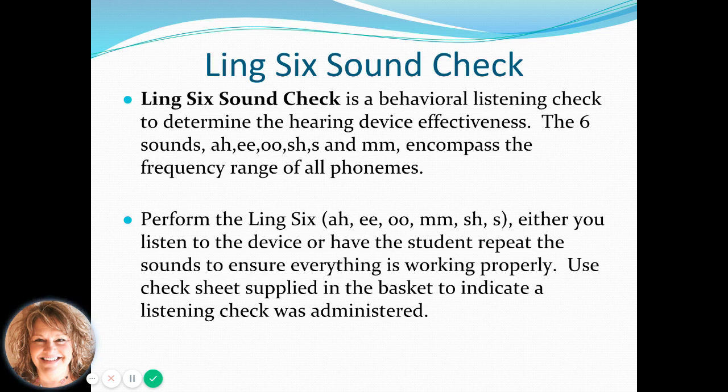You want to perform that either by listening to the device yourself and hearing those sounds, or having your student wear the hearing aid while you talk into the microphone at a distance and have them repeat those sounds. The main thing is to change up the sounds in different order. Don't always do the same thing, or you'll find that the student is just repeating what you say over and over. Even if it's a quick, hey, what'd you have for breakfast? Or depending on their age, you could say, touch your nose as you're walking away. Something where you know that the microphone is working and your voice is being sent to their hearing device, you know by how they respond that the device is working.